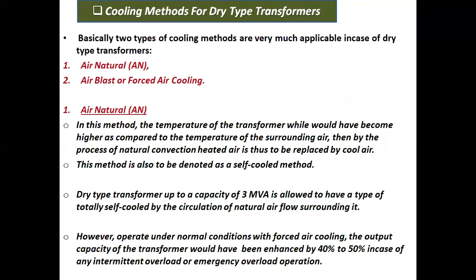Cooling methods for dry type transformer. Basically, two types of cooling methods are applicable in the case of dry type transformers. One is air natural, another is air blast or forced air cooling. Air natural: in this method, the temperature of the transformer becomes higher as compared to the temperature of the surrounding air. Then by the process of natural convection, heated air is replaced by cool air. This method is also denoted as a self-cooled method.